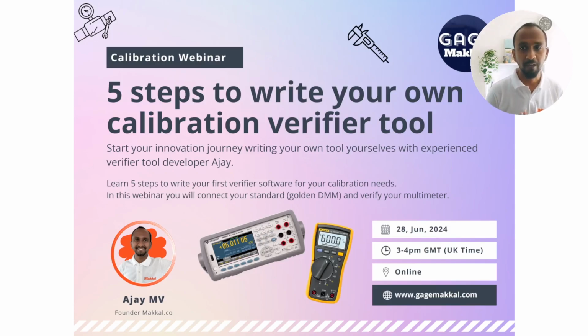So how do we go about writing our own verifier tool? In this webinar, we are going to look at using our own LabVIEW based tools to write a simple verifier that will test a multimeter and whether it is within the tolerance limits, and then it gives a pass or fail for the different tests that it carries out, and based on that we can do further tuning of the multimeter as we need.